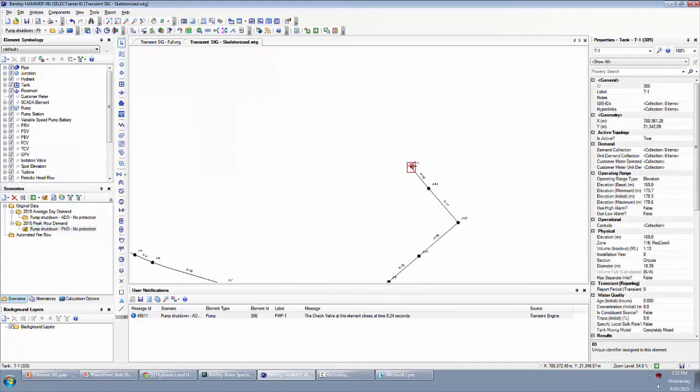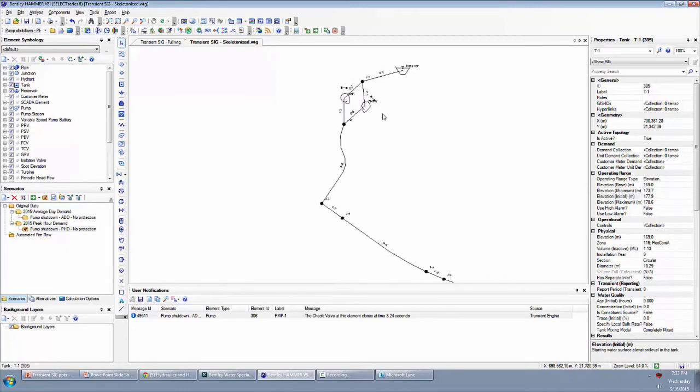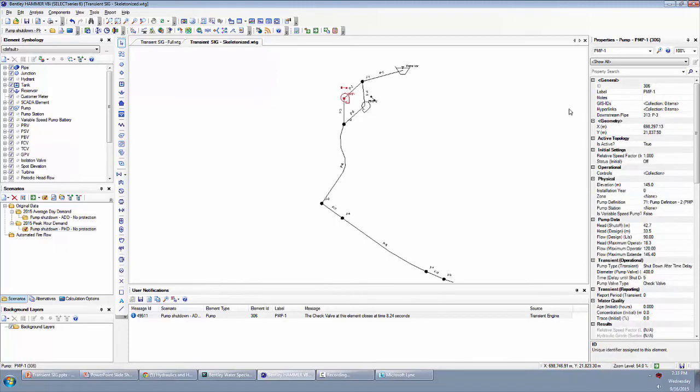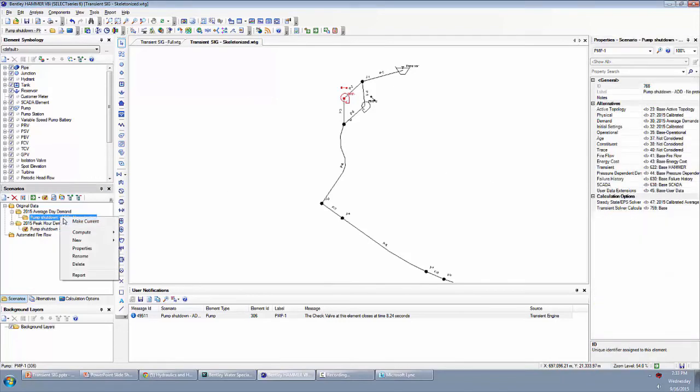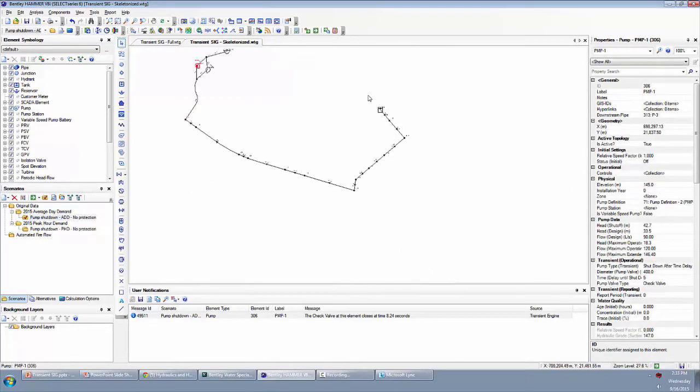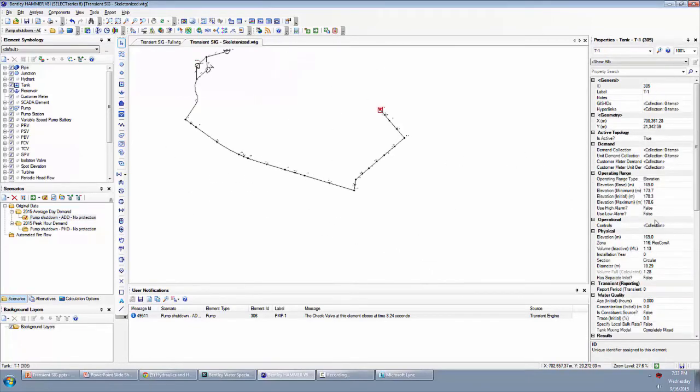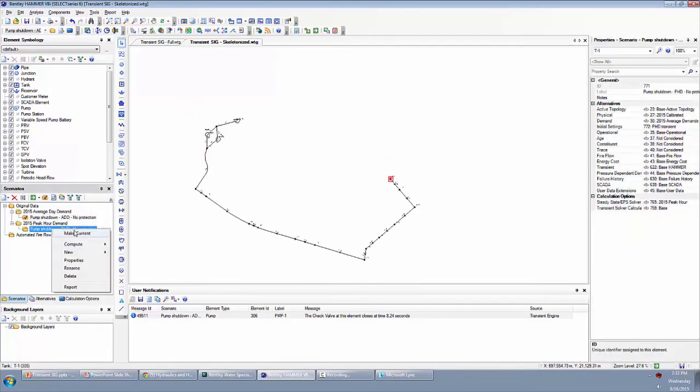So I'm going to set the initial elevation of our tank to be equal to that 177.9 that we started the last simulation at. The other thing we have to do is make sure that the pump in question is starting on. The initial status of a pump is also stored in the initial settings alternative. And just to show you, if I switch back to this scenario, the pump is back to being off and the tank has the old initial settings. They're tracked separately. You can keep these things separate and make changes over here without worrying about impacting the other scenario.